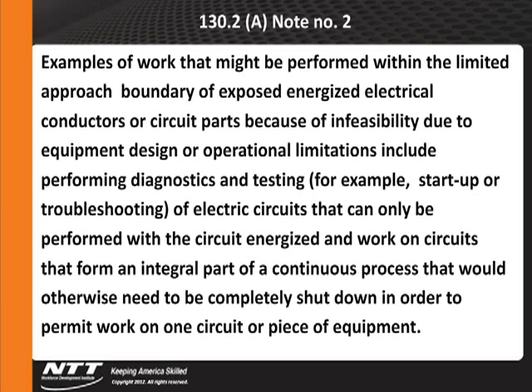It has to be on to do an amperage power factor study. But if you got a problem out there, flickering lights, in the past it would not be unusual. I'd go to a circuit breaker panel, you did your voltage test, you did this, and then somebody would pop a screwdriver out and see if the screws were tight on that circuit. That is not considered appropriate work. If that's what it is, that's repair and maintenance. It needs to be locked out, tagged out.